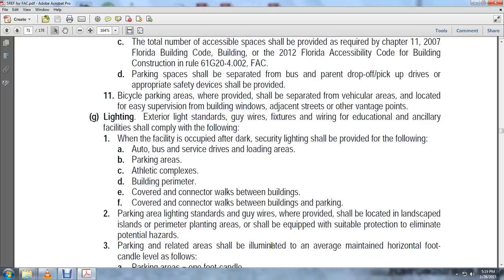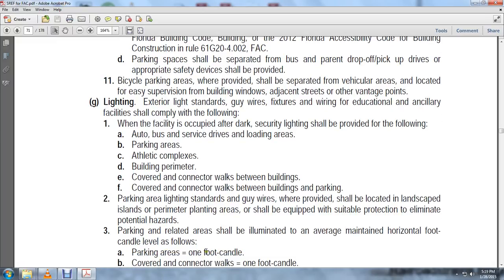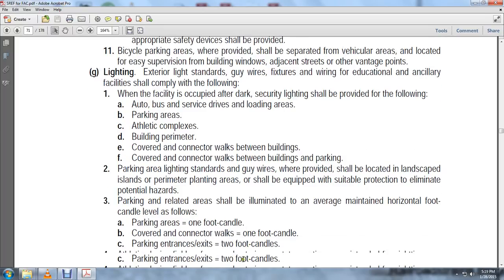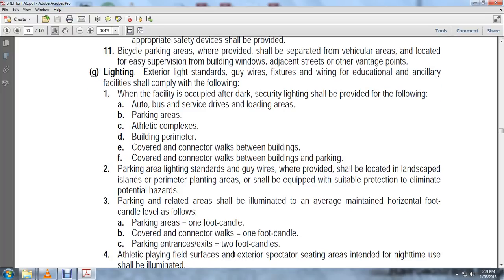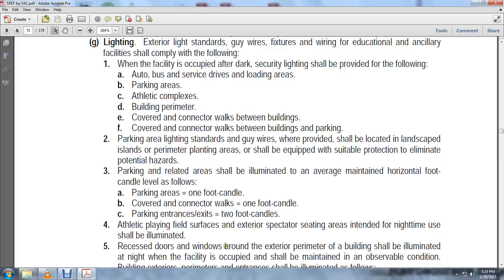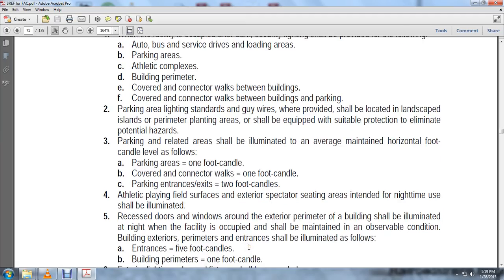Parking related areas shall be illuminated to maintain an average horizontal foot-candle level as follows: parking areas, 1 foot-candle; covered connector walkways, 1 foot-candle; parking entrance and exit, 2 foot-candles. Athletic playing field surfaces and exterior spectator seating areas intended for nighttime use shall be illuminated. Recessed doors and windows around the exterior perimeter of the building shall be illuminated at night. When the facility is occupied, it shall be maintained in an observable condition. Building exterior perimeters and entrances shall be illuminated as follows: entrances, 5 foot-candles; building perimeters, 1 foot-candle.